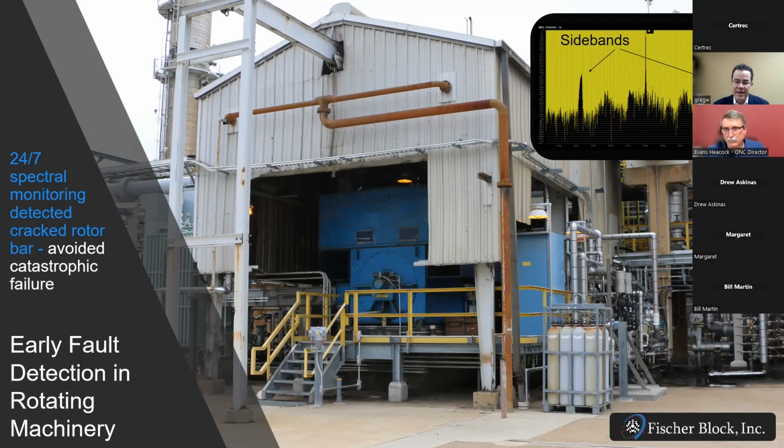So that slip frequency, plus or minus that frequency, is where our software looks around the fundamental. And as those sidebands grow, and a certain amount is normal, however, when they start growing in magnitude, that means those rotor bar imperfections are getting worse. And there are thresholds that industry looks for, and over the years there has been established thresholds.